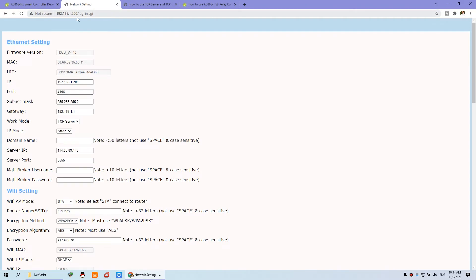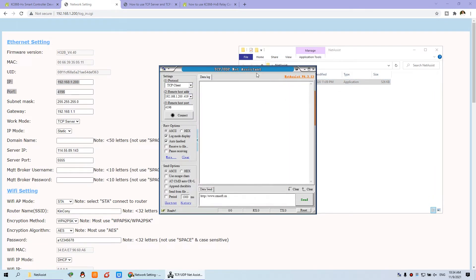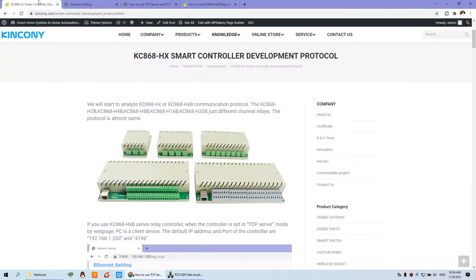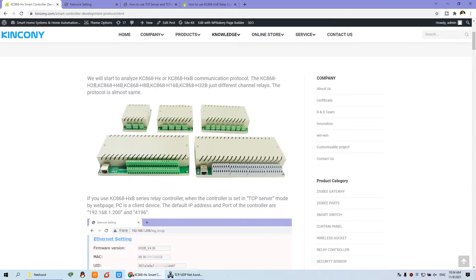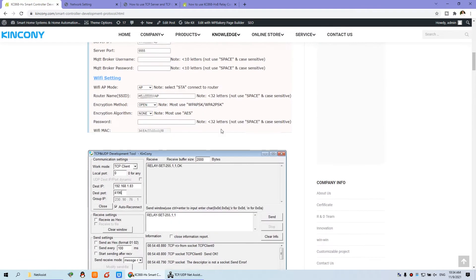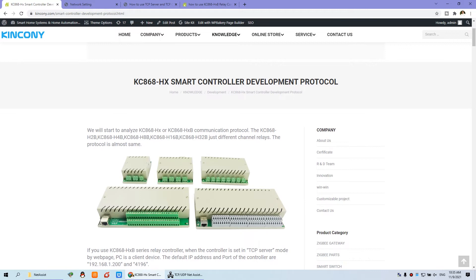I'll explain how to work with each mode. First, choose Ethernet for TCP server. You just enter your IP address in your web browser and you can see the Ethernet settings — the IP and the port. This is for use in a local network; your computer needs to connect with your controller. We can use a network debug tool — I have uploaded the network debug tool on our website — to test the protocol.